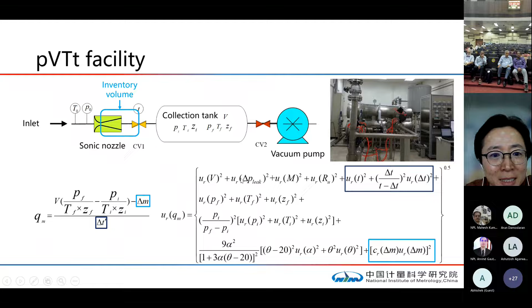But to guarantee the best uncertainty, there are additional uncertainty components. We call the inventory, the mass change in the inventory volume, and the additional time corrections for the filling time. So finally, the uncertainty of the Pvtt facility can be expressed like this. To achieve the best uncertainty for the Pvtt facilities, we make a lot of work. Finally, with the special designing of the three-way valve, we achieved the mass cancellation in the inventory and minimize the time corrections. This is the structure for the three-way valve.